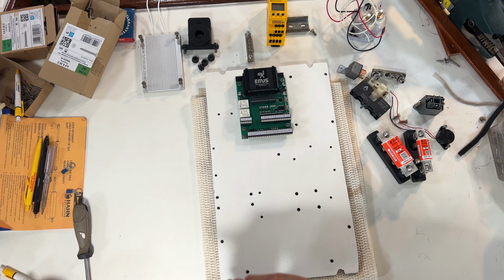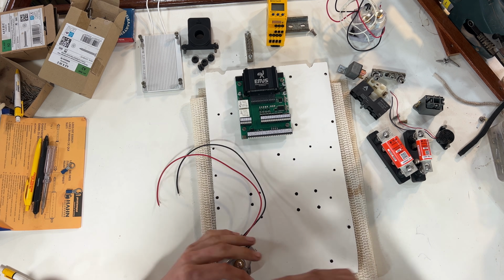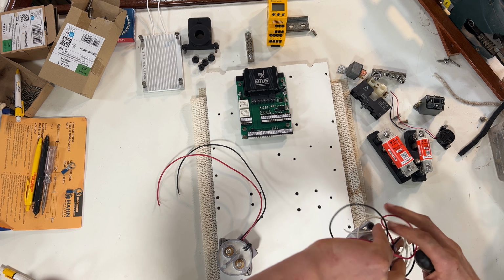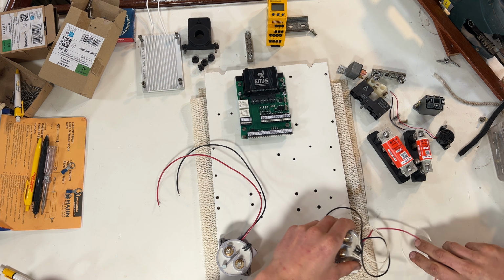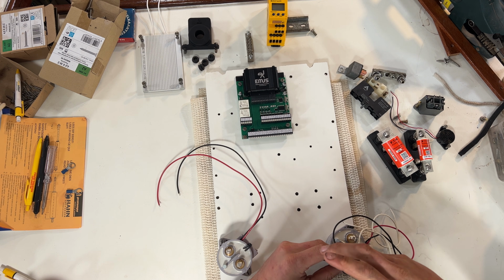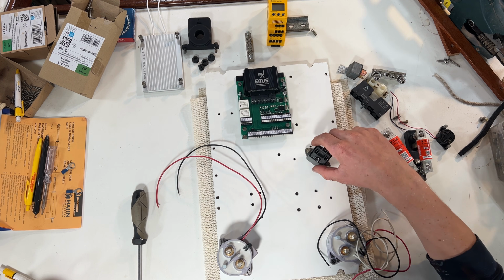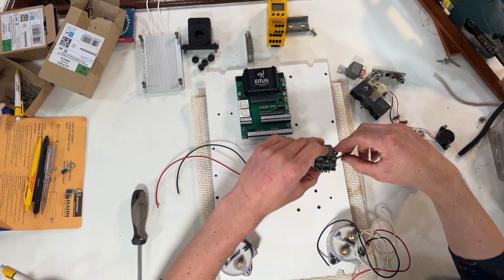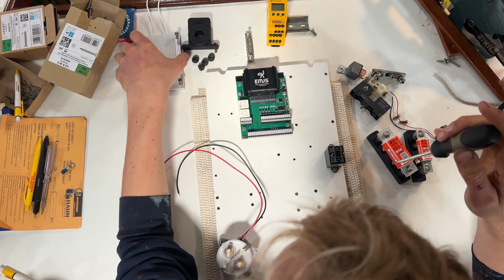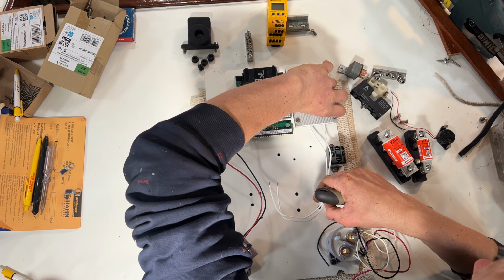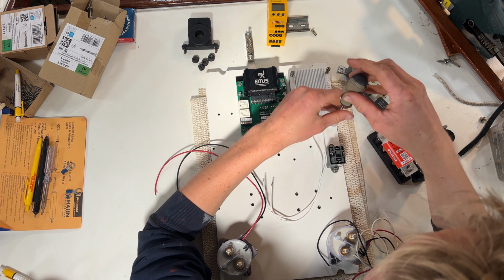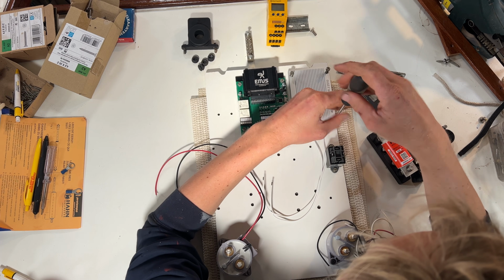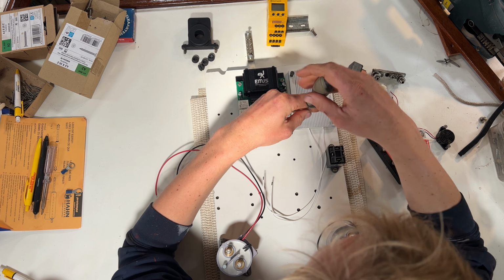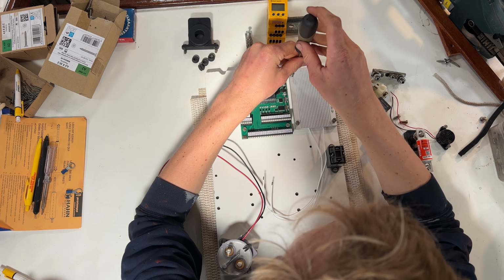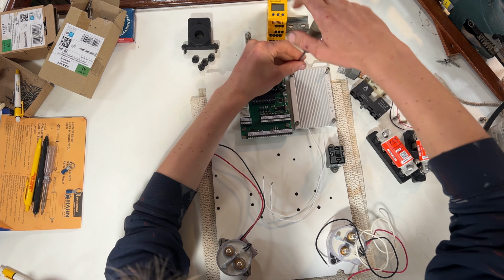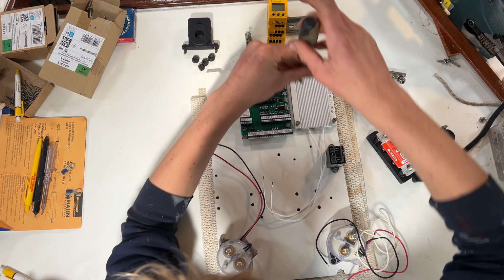Then we have the 2 main high voltage contactors, one in the positive line and one in the negative line. The BMS decides if they're allowed to close, and it opens them immediately if anything is outside of safe limits. Next to that is a smaller high voltage contactor, controlling the pre-charge. When the BMS gives green light, this one closes first, feeding the entire system through this resistor, this big flat thing. So the capacitors inside the motor controller and the chargers can slowly rise to pack voltage. Without pre-charge, closing the main positive contactor would cause a huge inrush current as the whole system jumps to 400 volts in a split second, which is very bad for everything downstream.